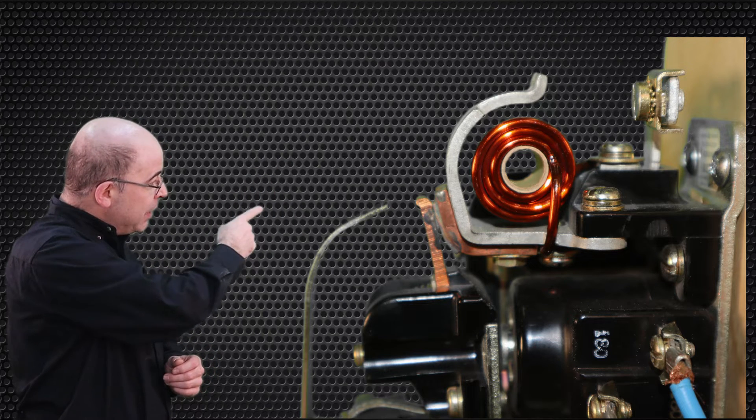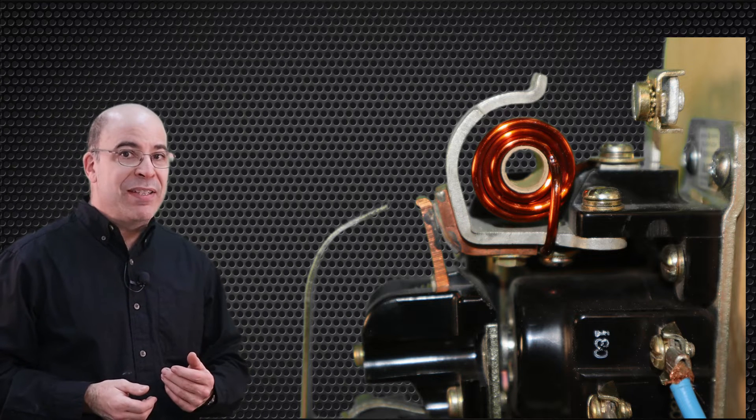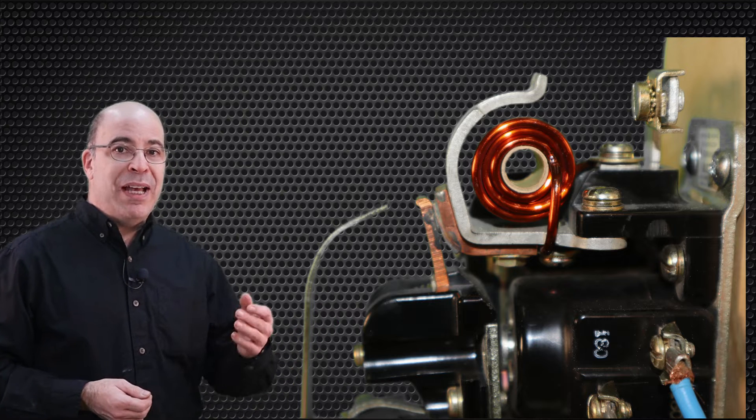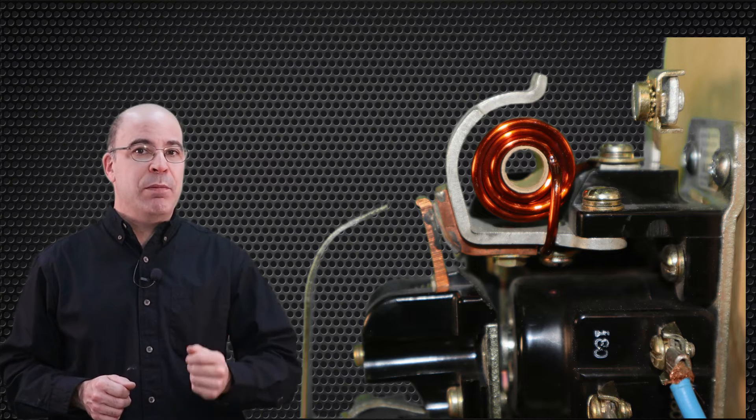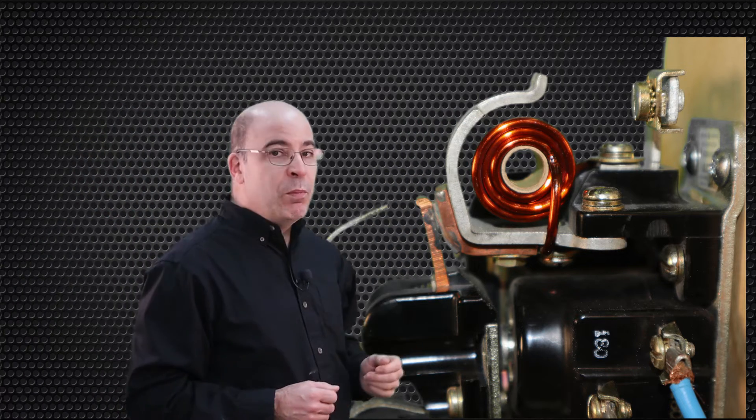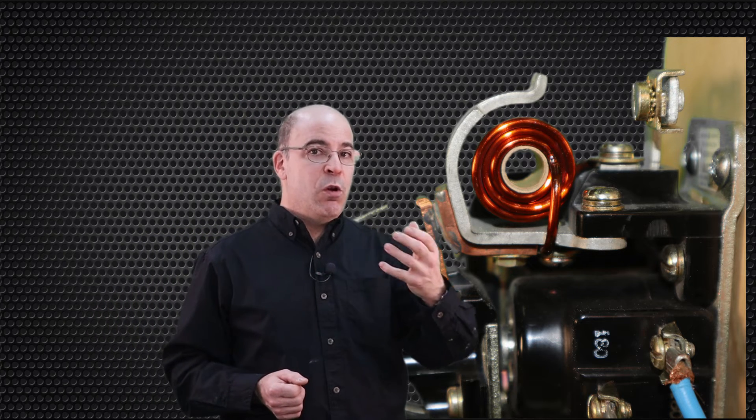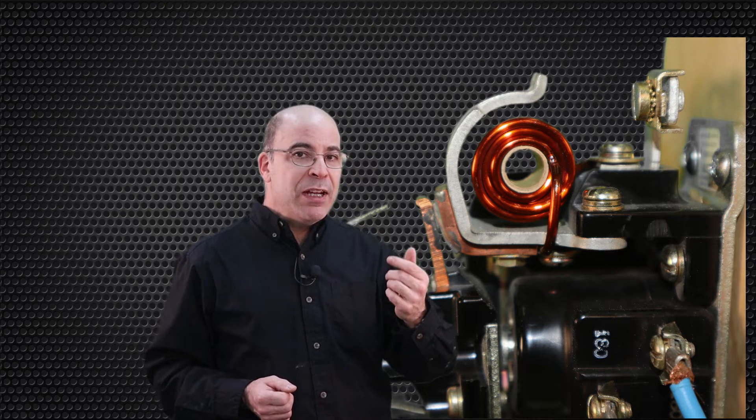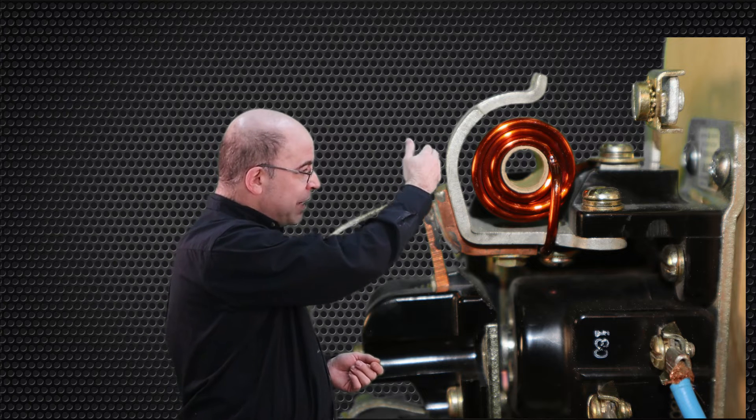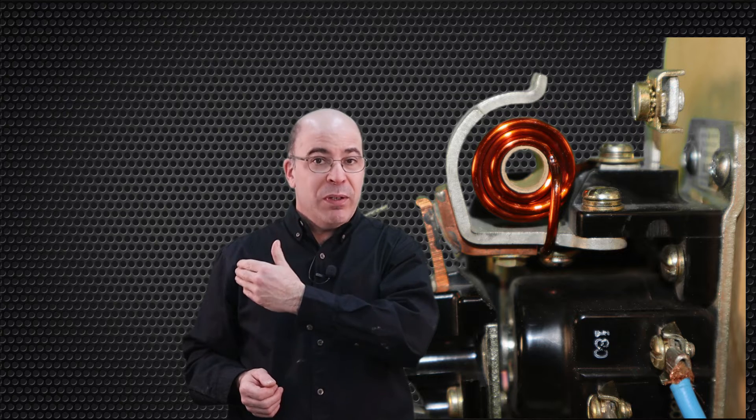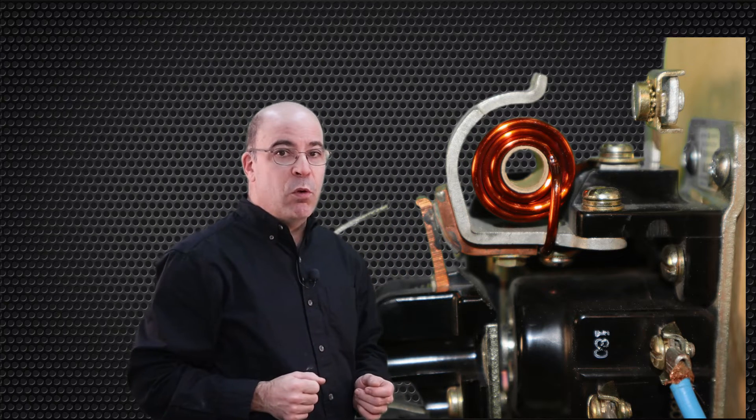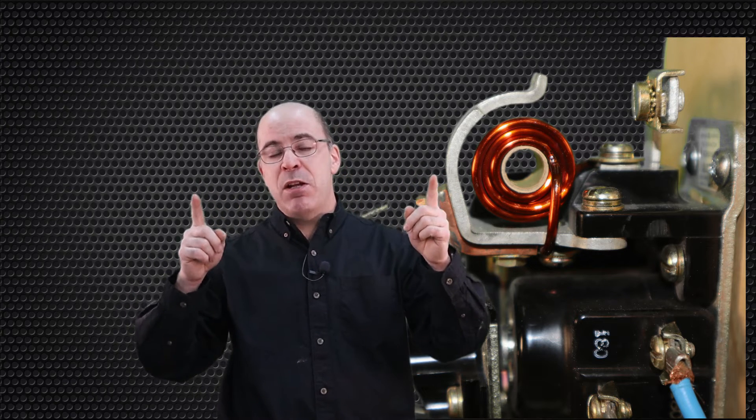The curved piece of metal that is in close contact with the main contactor or the movable contact, it's not there by accident. It is there to allow for the current to basically jump from the contact onto the metal to help stretch it out. But now, how do we get that arc to move in a predictable pattern? Well, that's by using what we call the blowout coil. When current is traveling across an open air gap, we still have current flow. That current is flowing through the air gap across this metal piece and is flowing through this large conductor wire that is turned up into a coil. That is going to create a magnetic field of opposite polarity to the magnetic field or the current flowing across the contacts. That's going to draw that arc in a predictable pattern up towards that blowout coil, stretching the arc, lengthening the arc to the point where it may not be able to sustain itself. That is the whole goal behind the design of this type of contactor.